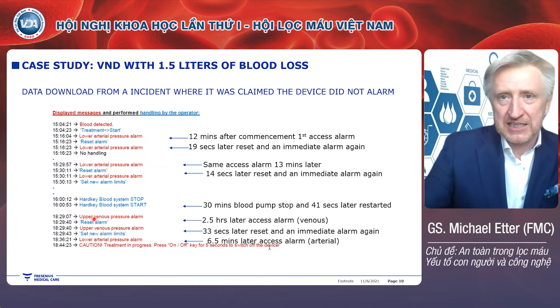And that went on for a little while, and then you see something very risky, which happened here at some moment, because the alarms came in a rapid sequence. Somebody decided to reset the alarm limits. And that actually then led to a situation where the patient lost 1.5 liters of blood because of a venous needle dislodgement. Here's what I'm talking about.